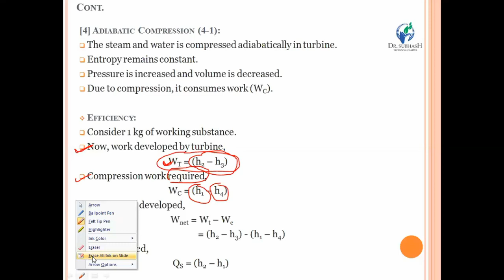Similarly, you also have to calculate the compressor work that is required to run the compressor. So once again, we have to take the difference of enthalpy. At the outlet of the compressor, there is a higher enthalpy. At the inlet of the compressor, there is a lower enthalpy. So its difference gives the compressor work, or the power required to run the compressor.